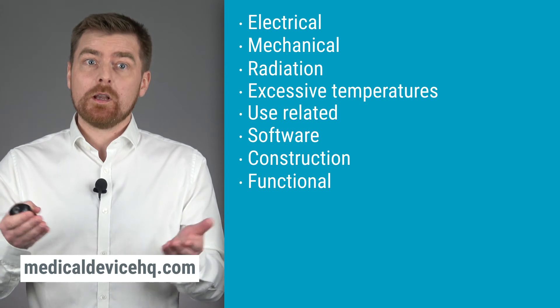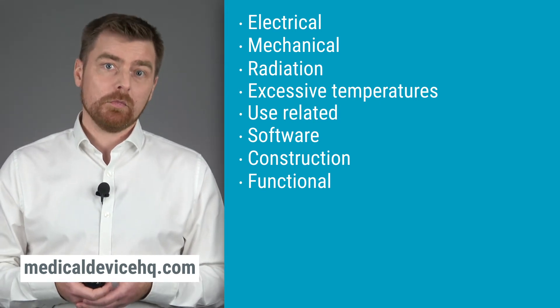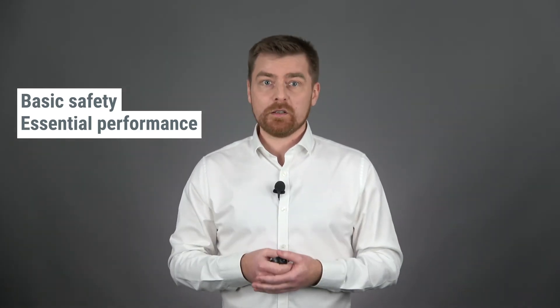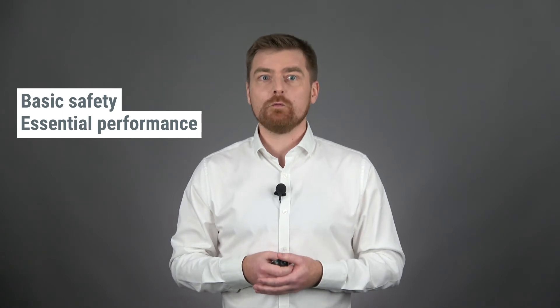See our course on risk management at medicaldevicehq.com to find out more. So if your medical device falls within the scope of IEC 60601-1, you are going to have to pay attention to all these requirements and reach at least the levels defined in the standards. Because if you don't, not only do you risk injuring people, but you are also likely to not meet the legal requirements for placing your product on the market. The goal with all of this is to ensure basic safety and essential performance, which basically means that patients and other users shall have freedom from unacceptable risk.